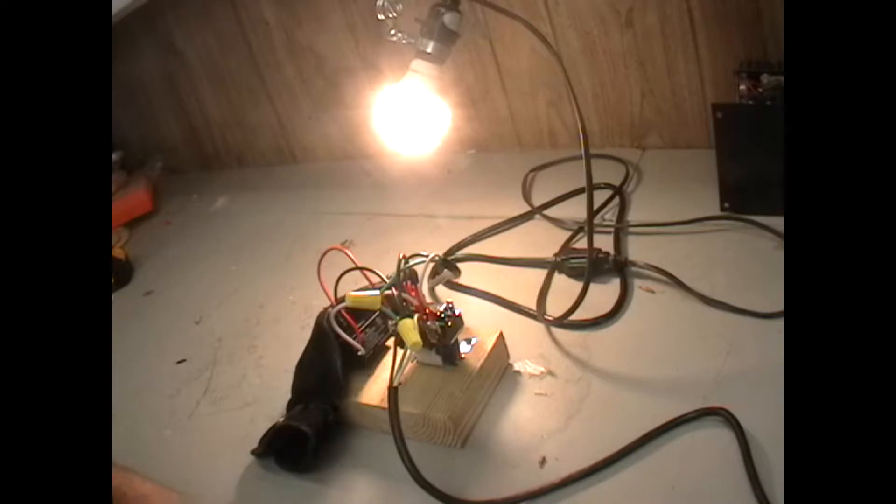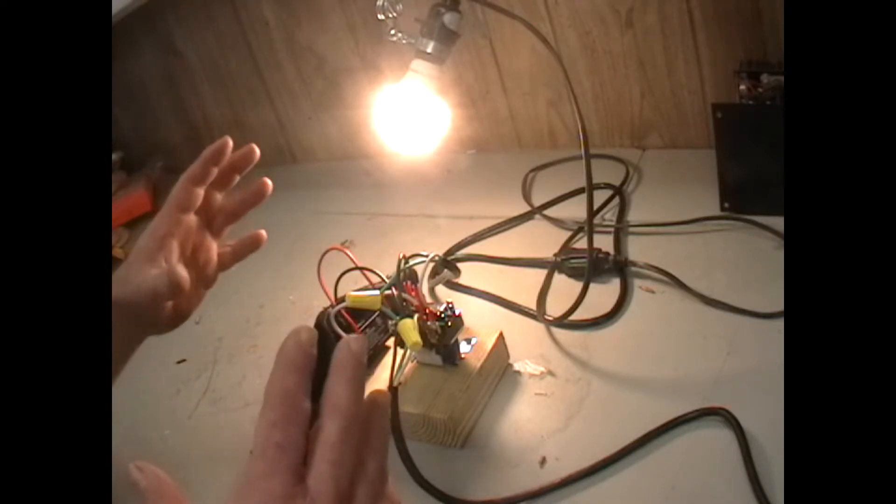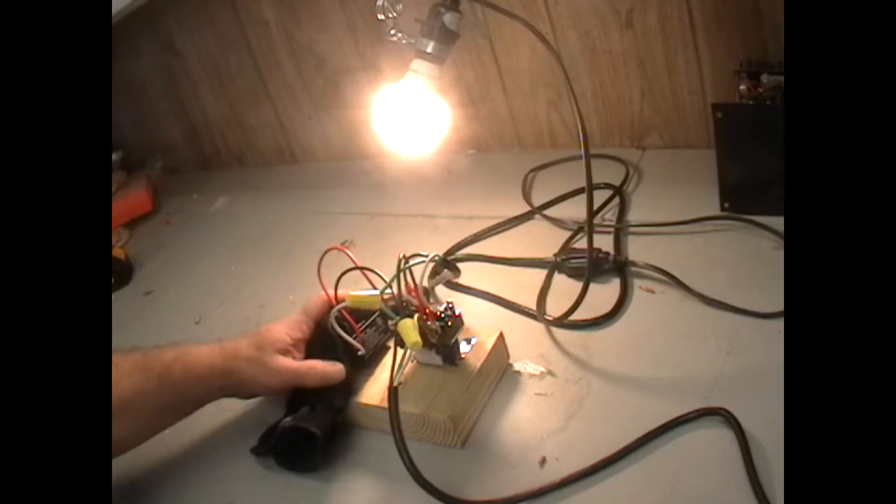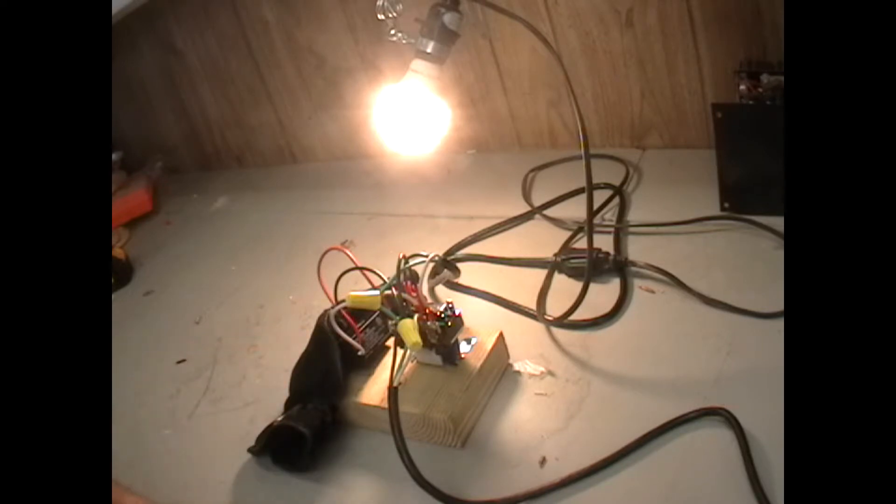So what we're doing through the day, we've got a normally closed circuit that keeps our device on, and then when the photocell engages when it gets dark, we're sending the power that we would normally send to a light to this relay, and the relay opens the contacts so that our device shuts off.